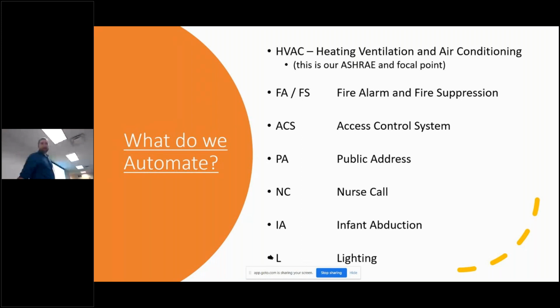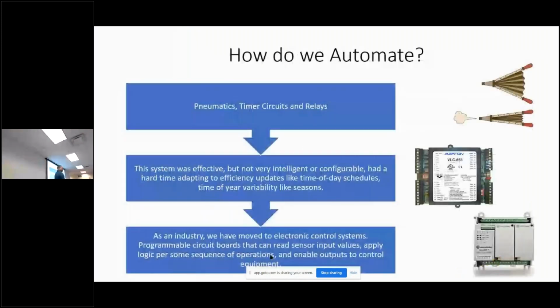In the world of HVAC, how do we automate? For the longest time, it was a system of pneumatics, timer circuits, and relays. Pneumatics is essentially a system of tubes running throughout a building maintained at a certain pressure, used to trigger relays, actuators, and mechanical components to produce the desired outcome. Air pressure would turn valves open and closed, and trigger relays to turn fans on and off. It was actually pretty sophisticated in its heyday, but it had inherent issues—it was effective but not very intelligent or configurable, and had a hard time adapting to complicated occupancy schedules.